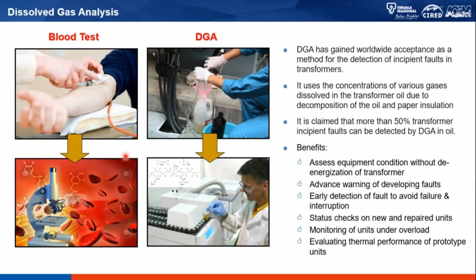So just now we talked about 70% of the operational data can come from the oil. By doing DGA, it is claimed that more than 50% of these incipient faults in the transformer can be detected through DGA. So that is actually quite helpful, as compared to perhaps doing visual inspection on our transformers.